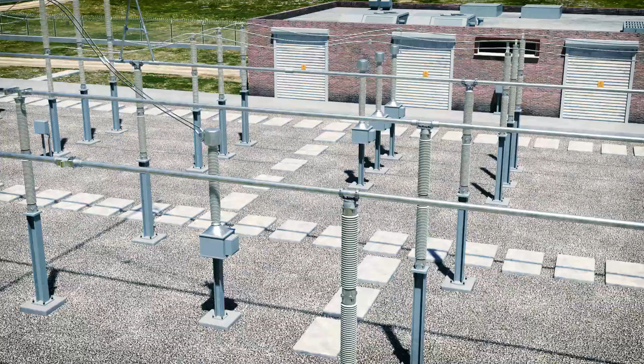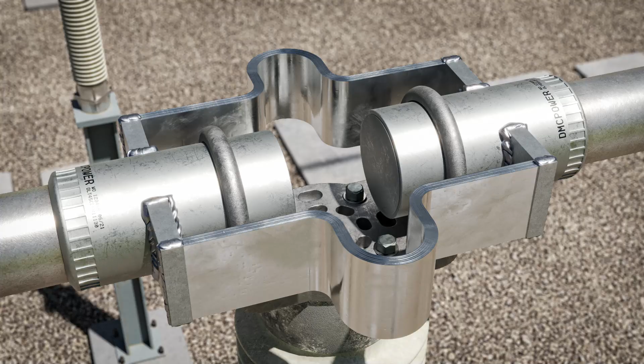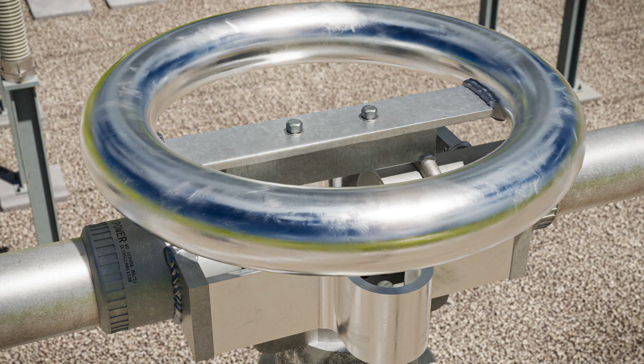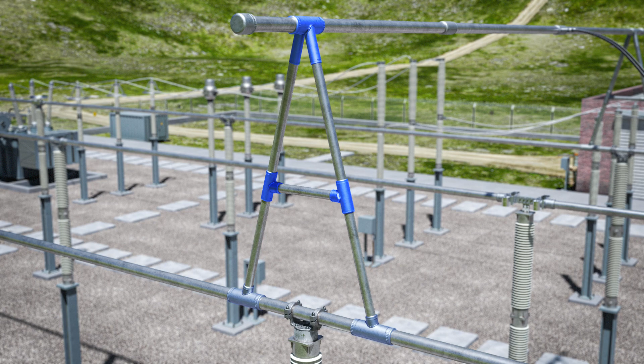This is the structural part of the substation and includes terminals that connect to equipment and other terminals to continue the electricity flow, supports to physically hold the bus tubing in place, expansions which allow the tubing to safely expand with heating and cooling cycles, and various components for A-frame structures to further route the electricity.